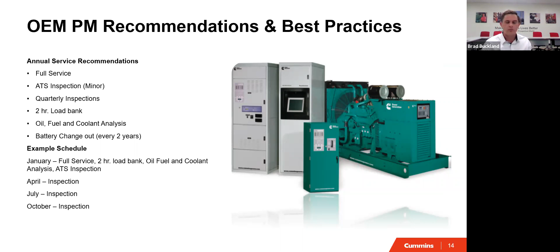So how this works is this load bank here on the right, it's just a resistive load bank. They're designed to just test the generator and simulate a generator taking on a building's load. That load bank will be rated the same rating, so the same output as your generator is. And we test it at certain intervals, disconnecting it from your main building, so you still have utility power, it won't inconvenience any customer you have. And we test it as if there was a failure in the building.